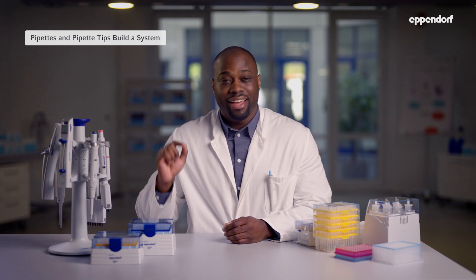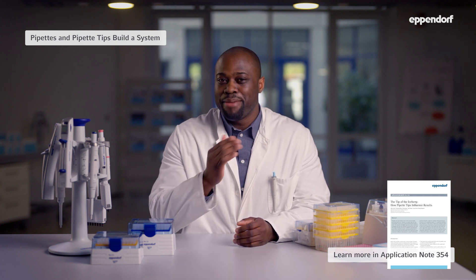According to ISO 8655, the international standard for pipette calibration, pipette error data applies to the total system made by the same supplier — that is, the pipette and the pipette tip together.